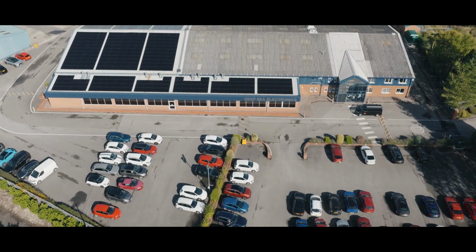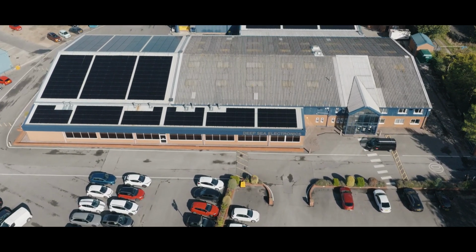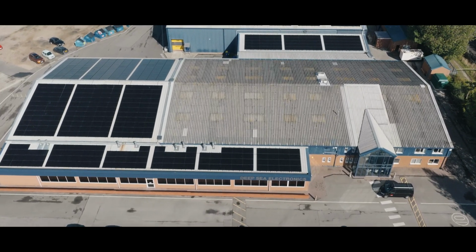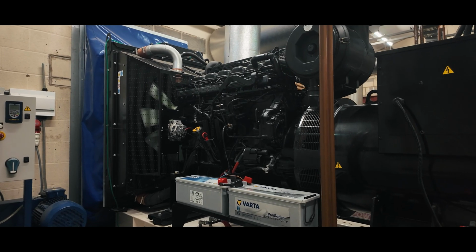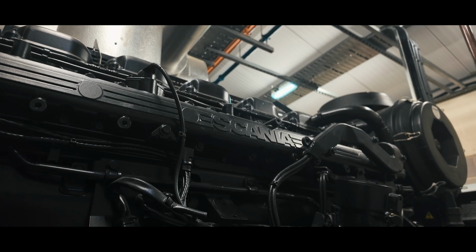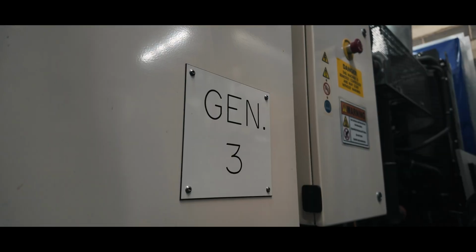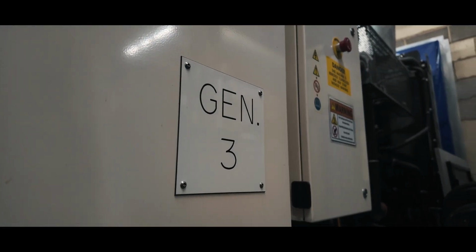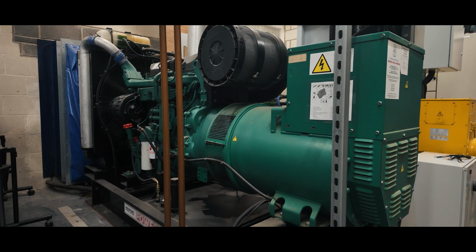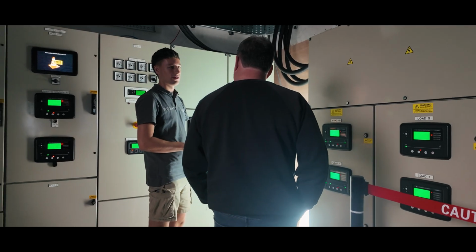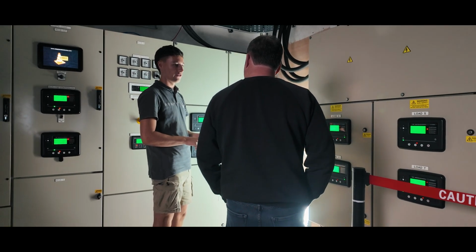The general layout at Deep Sea is we have a main supply from our own transformer, which is fed into our switchgear. We also have availability for emergency generator backups, plus the load from the PV. Just recently we've had a site UPS installed, which in the event of brownouts or blackouts will cover the time it takes from the mains going off to the generators coming online and supplying factory load.